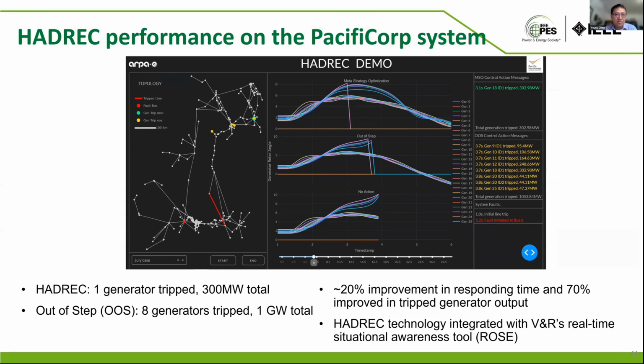So in particular, for this event and HADREC, for this condition, we tripped only one generator, about 300 megawatts, tripped at about 3.1 seconds. You can see it in the right corner here, 3.1 seconds. If you use the out of step actions, they will require 8 generators tripped to bring the system back, and the total amount of generator capacity tripped is about 1 gigawatt. So we can see it's about 20% improvement in terms of responding time.